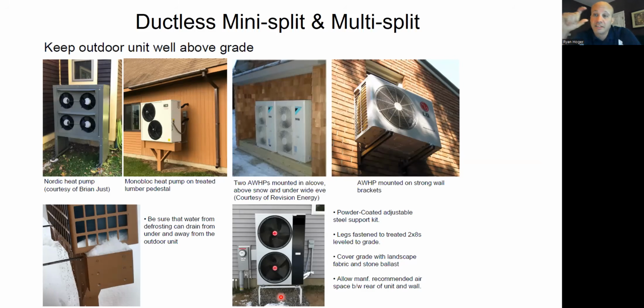For one, I need it raised up a little bit because there's going to be a drain on there. A normal air conditioner does not have a drain on it on the outside unit. The indoor unit does. The indoor evaporator coil does, but the outdoor unit doesn't. But a heat pump, remember, the evaporator and condenser switch jobs. So now in the heating mode, my outdoor unit is the evaporator coil, which means condensate's going to form on it, and that's going to drain down. It needs to go somewhere. So I got to raise the heat pump up a few inches in order to have that drain be able to come out the bottom of it and then go away.